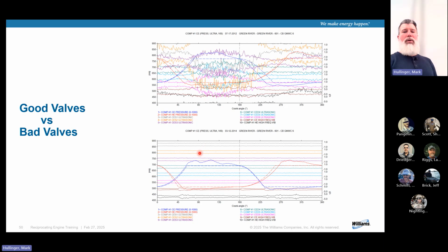And so we budgeted for new valves, and then we did a cost benefit analysis. And this particular station with 4 recips gained 13 million in additional flow, just in efficiency. And so the math on that worked out to a 2-day payback. So you buy a valve and in 2 days, you've made up for it in flow.